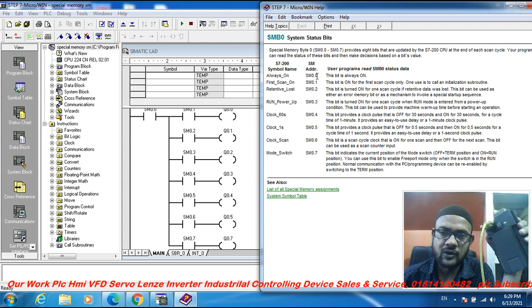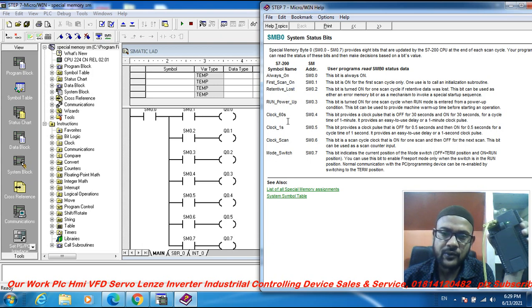SM 0.0 is the always-on switch. SM 0.1 is the first scan on. SM 0.2 is the retentive data lost bit. SM 0.3 is run power-up. SM 0.4 is the 60-second clock. SM 0.5 is the one-second clock. SM 0.6 is the scan cycle clock.